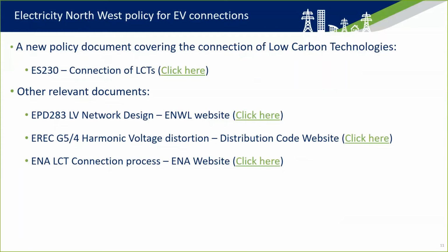Behind that, we do have other Electricity Northwest policy documents. So EPD 283 just covers LV network design in general, so connections would have to comply with that as well. And then there are more national documents. So I mentioned Engineering Recommendation G5. That's also available to download from the Distribution Code website. ENA connection process, there's another link to it there. And finally, I put on there MOCOPA, the Meter Operators Code of Practice Agreement, produce a guidance document, which originally was intended for meter operators and people working at the service position, but it does give some guidance on some of the things to look out for, typical defects or faults at the service position. That's free to download, and the link is available there.